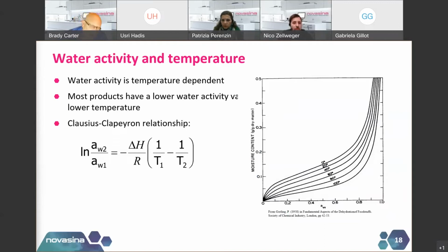Because what can happen is, if the conditions in the testing area, laboratory, whatever it may be, vary throughout the year, then you'll see changes in your water activity values matching those changes in temperature. So if part of the year you're at 20 C and the other part at 26 C, those will give two different water activities. By having a water activity instrument that controls temperature to say 25 C, that prevents the fluctuation that could happen.